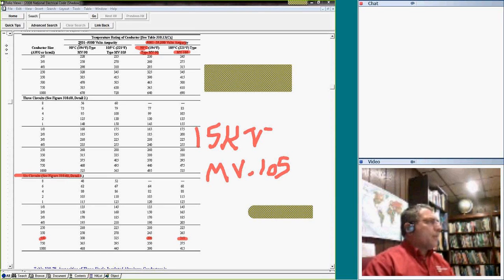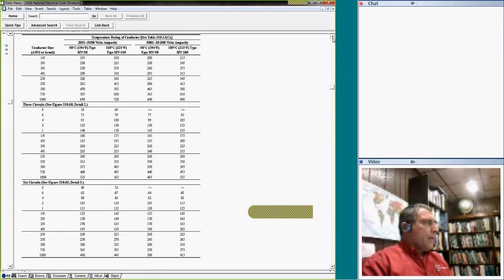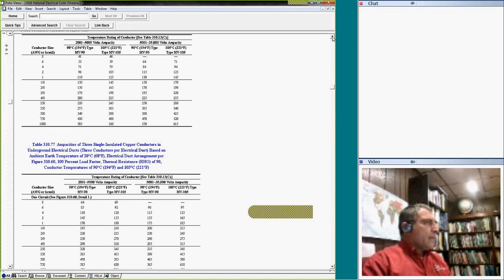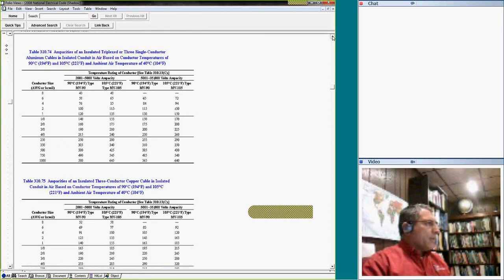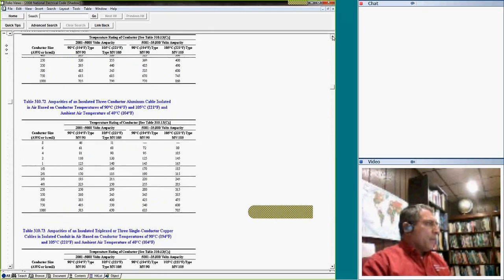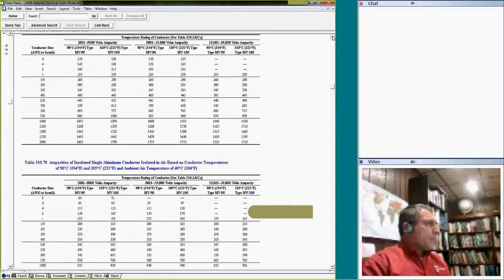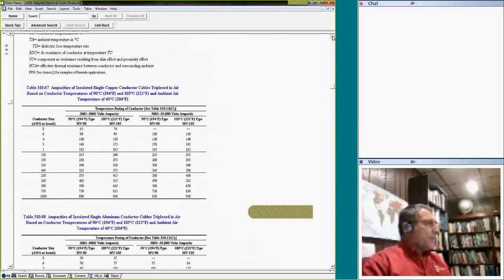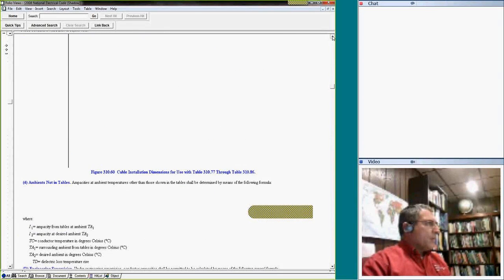About this medium voltage cable, if you're dealing with medium voltage, guys, these become very handy. Okay, this is only for 6 ducts carrying 6 circuits. Each one is 3 phase per duct. So interesting as you move through. And one I want to follow here, so all the medium voltage cable, if you're in medium voltage cable, this is your baby. So I strongly suggest you review. If you have any question, call me. I've used a few of them here over the years. So I'm going to go all the way. Here's the configuration, direct buried, all the way.